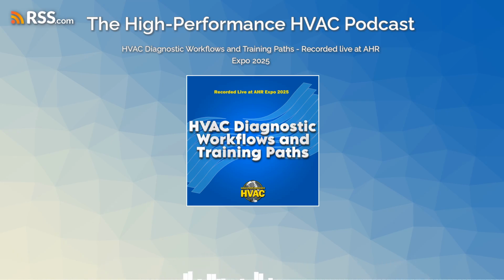Can you explain the history of the air upgrade and how it came to be? Sure. So NCI has been teaching air balancing, air diagnostics, and that sort of thing for about 30 plus years. Just about five to six years ago, we looked at what can you do to a system, almost like, I don't want to say the bare minimum, but what key things can you do to make sure the equipment is actually operating in the range it should be operating - like it can breathe, static pressures, get the right airflow, and that sort of thing. And then checking the charge if it makes sense. If you've got your deltas and everything, you're good to go.